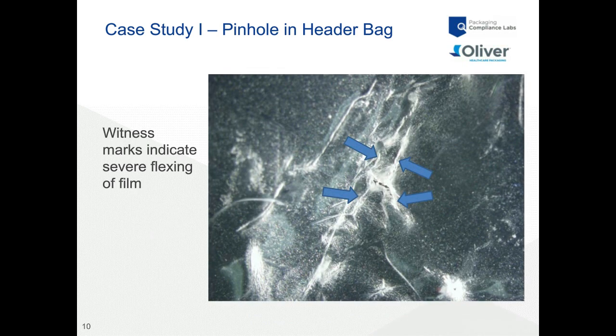So the nature of the defect is really important. You can see the breach of the sterile barrier here, obviously a hole that failed probably a bubble test. But as you look around the perimeter of that breach, it starts to tell you a story. Don't always default to thinking there was a puncture, that the device or something externally must have punctured the pouch or package film, in this case a header bag.